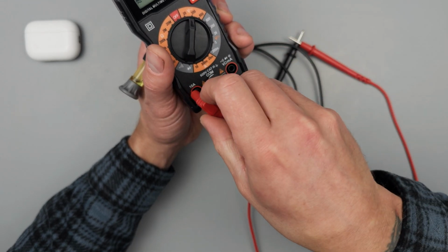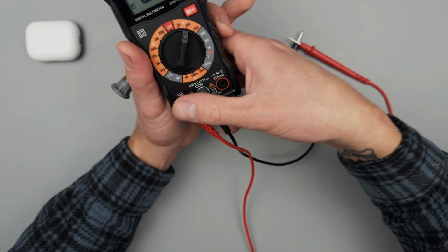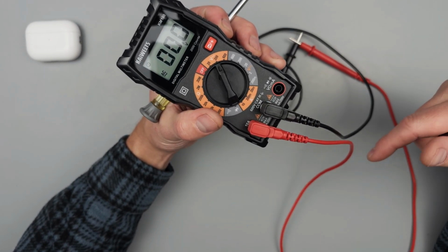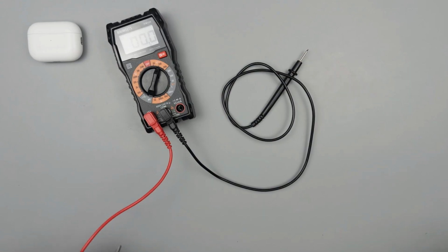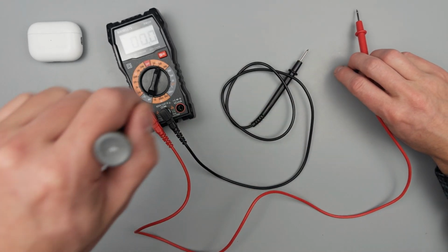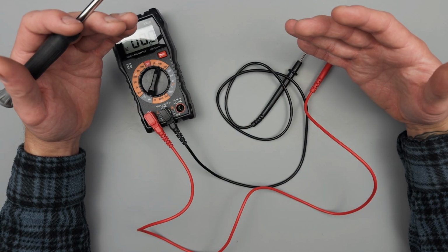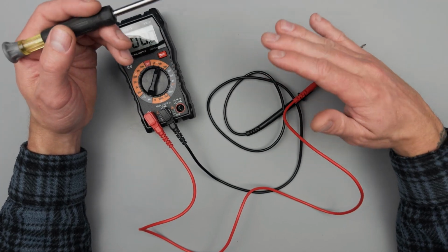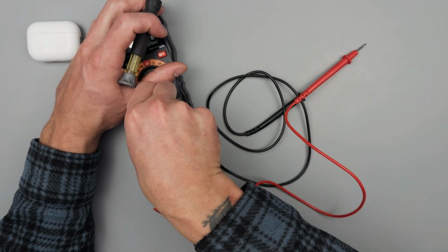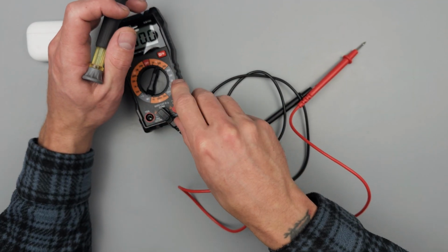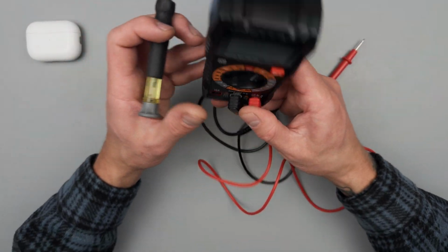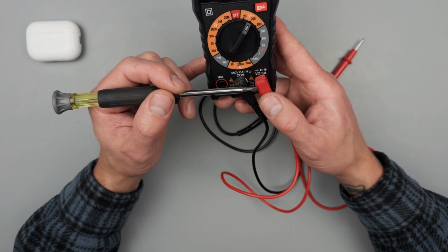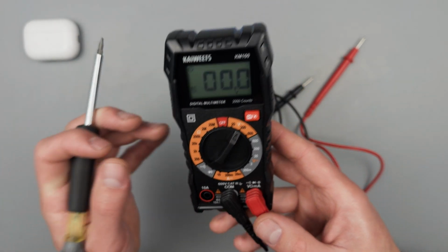When we configure the meter like this, now we've converted the meter into a jumper wire that can measure current. There's continuity through these wires all the way through, almost no resistance. So that's what's causing people to short things out. It's a really common mistake, and it can give you confusing measurements. So we want to make sure these leads are fully seated, and we want to pay attention to which port our red lead is plugged into.